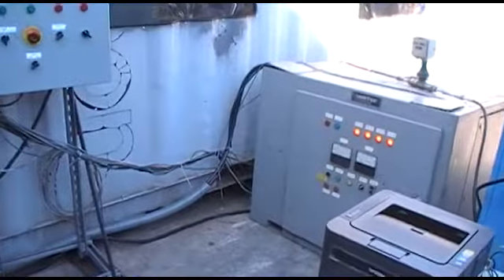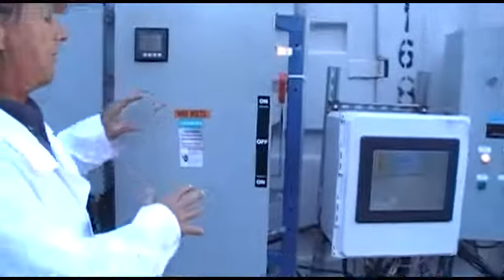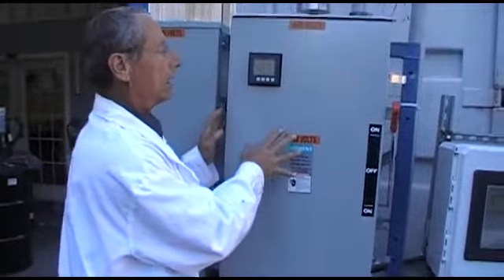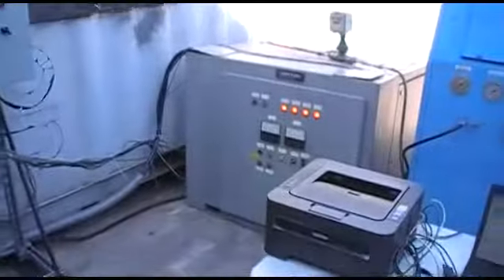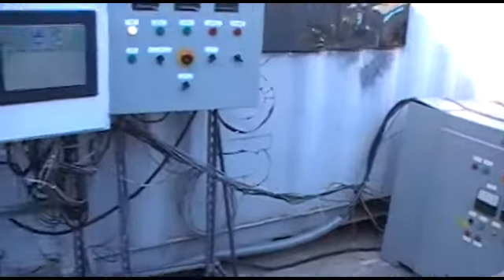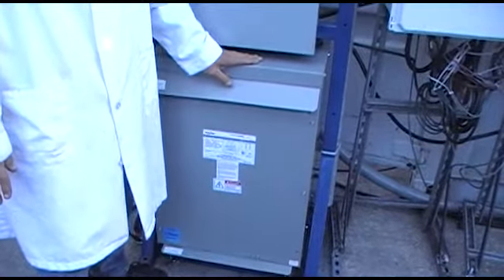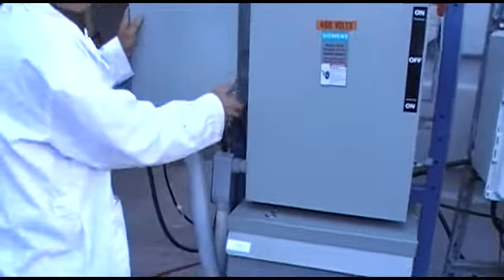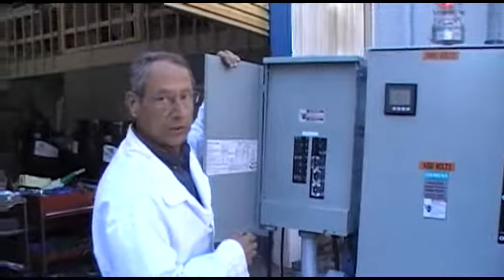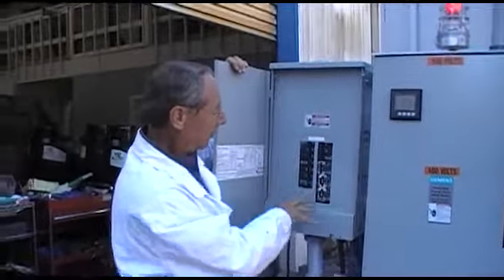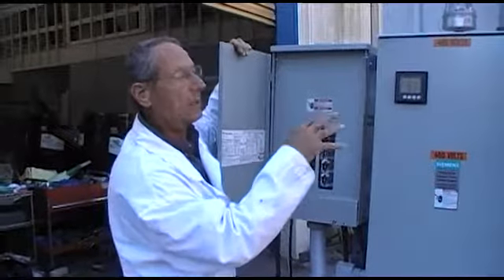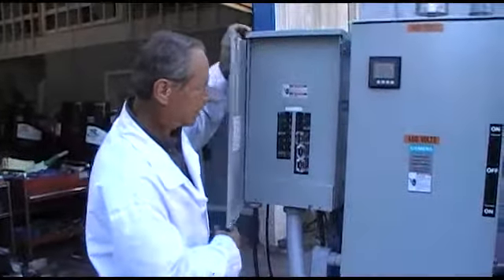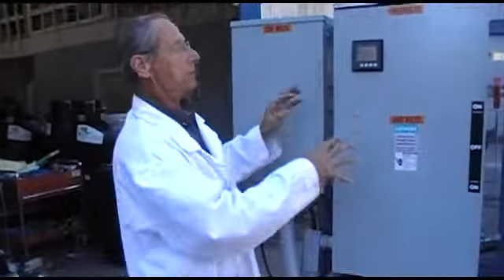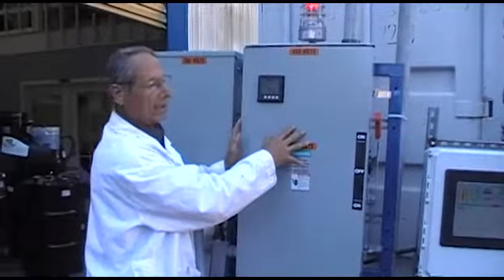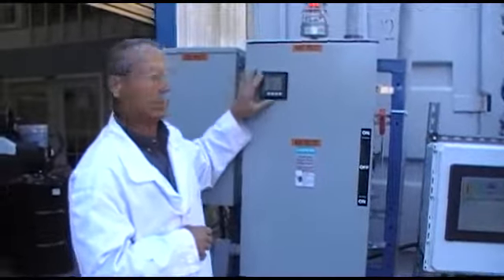We have several power requirements in the reactor, so we distribute the main power from this box. The 480 volts from this box feeds the Ametek power supply. We also take a feed from this box to a transformer that brings the voltage down to 240 volt 3-phase, which is redistributed at lower voltage to the other equipment through this panel, feeding the lower voltage equipment plus all of the controls. Everything is wired per code, and by feeding it this way, we know all the power consumed is being recorded by this meter.